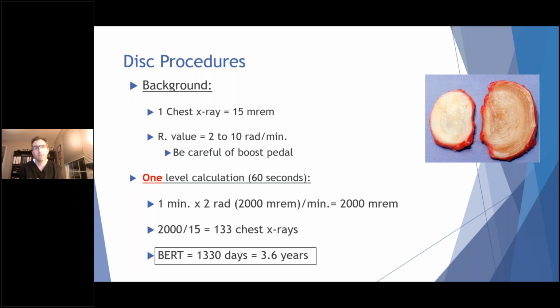You have one chest X-ray, which equals anywhere between 10 to 15 millirems. Now, when you step on the pedal for your machine, depending on how it's set, it puts out anywhere between 2 to 10 rads per minute if you step on the continuous fluoroscopy pedal. Again, it depends on whether you press the boost button also. But even if you don't press the boost button, it's anywhere between 2 to 10 rads per minute. If you did a 1-level discography, and it took you 60 seconds of live fluoroscopy, 1 minute times 2 rads equals 2,000 millirems.